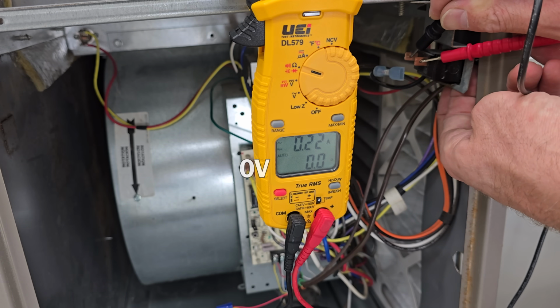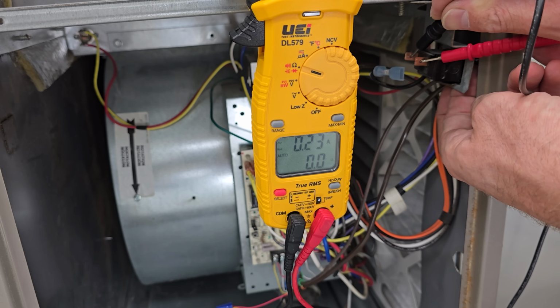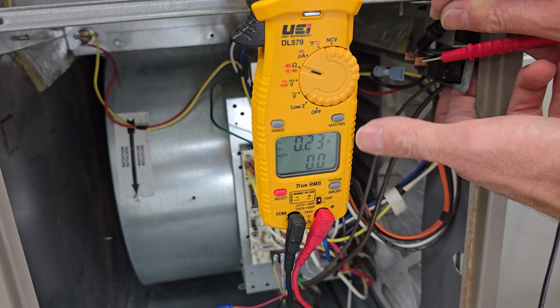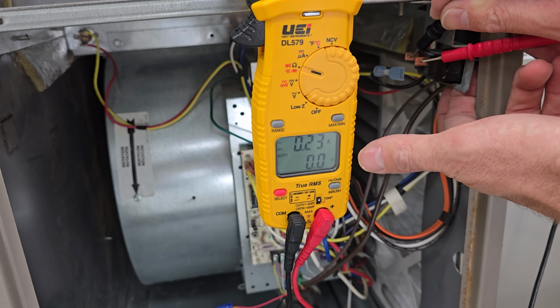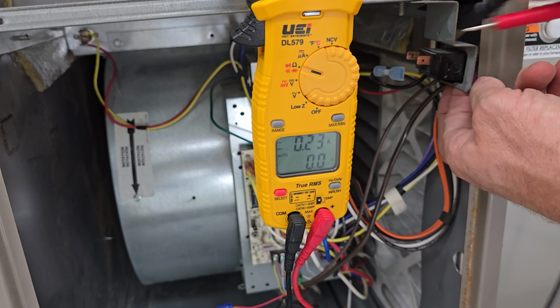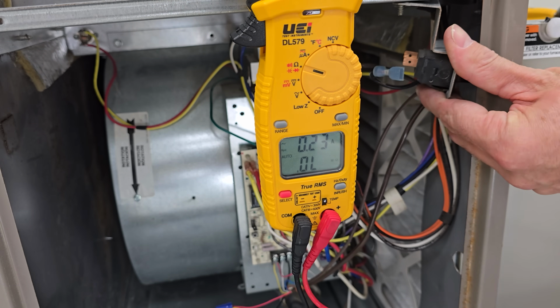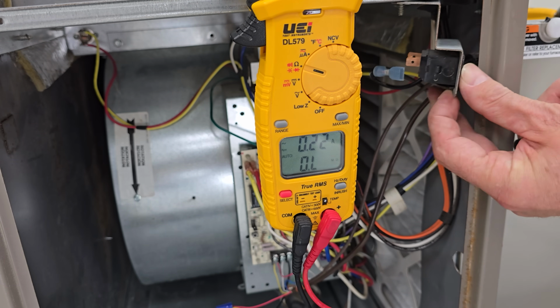So that tells you that we have a good switch, but we could end up having a bad switch where we have a very high electrical resistance across it, as if it's open even when it is closed. So that is something to keep an eye out for when you are diagnosing.